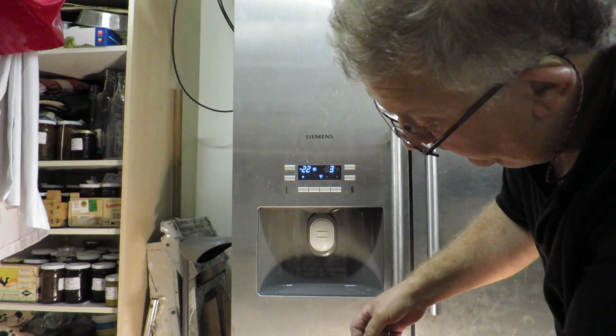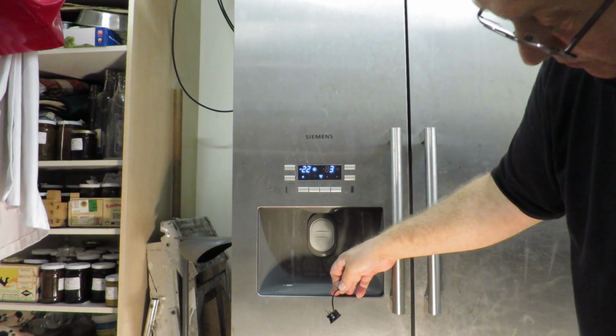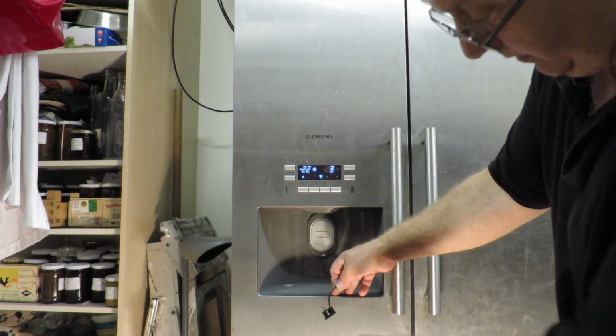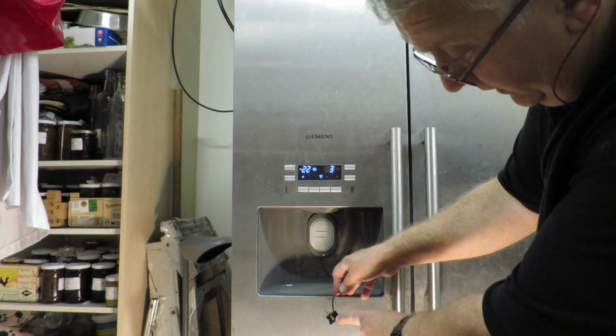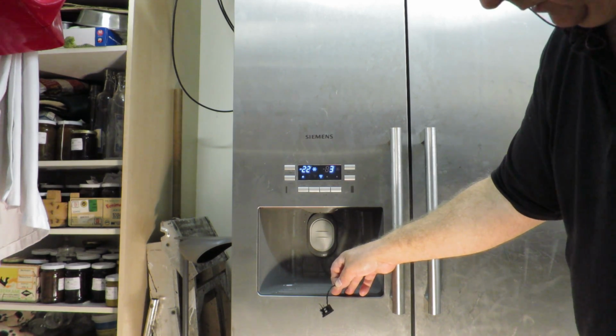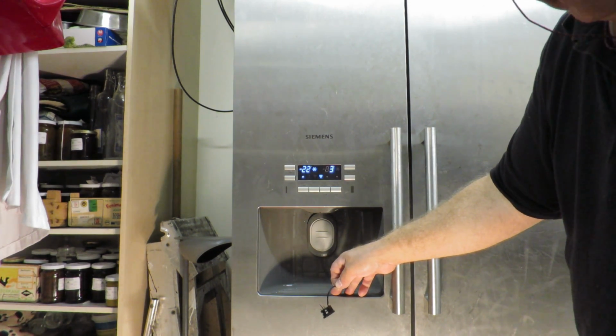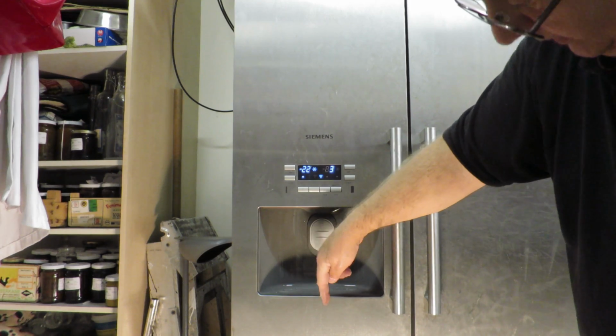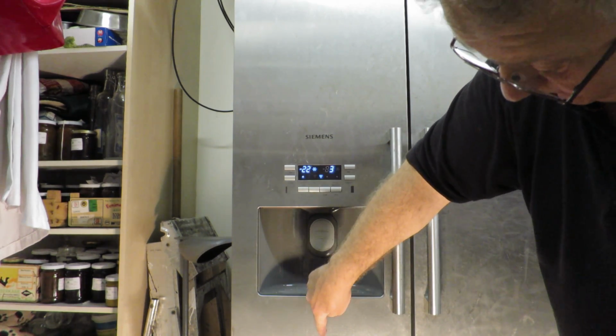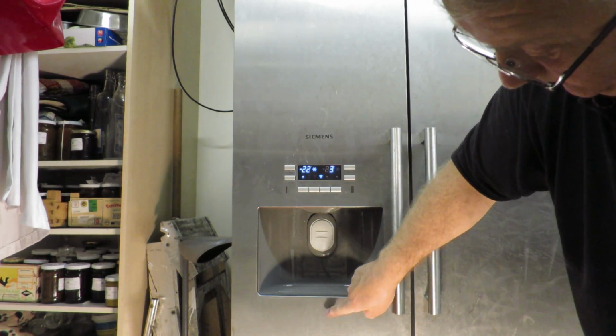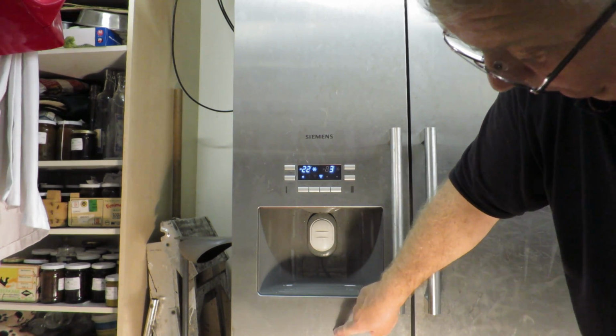All this does is, if you put an AVO meter across it, it's a short, but if too much current is pulled through it, this will cut off the supply to the compressor. So that's ingoing to the compressor, that's the top pin. The compressor has two coils, a start coil and a run coil.